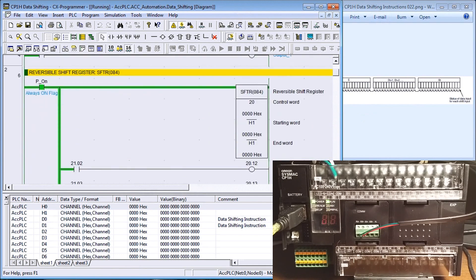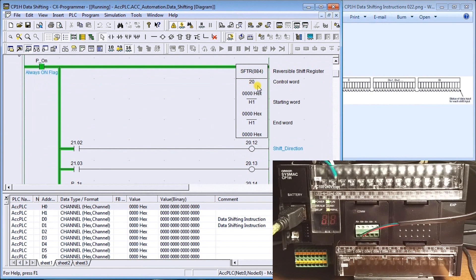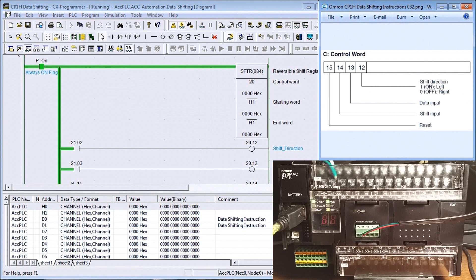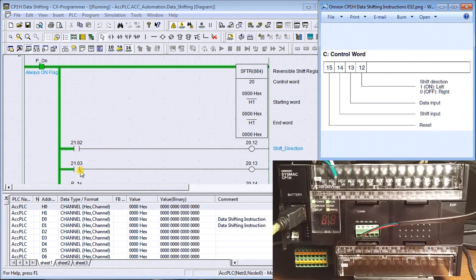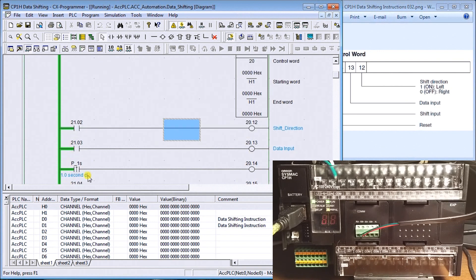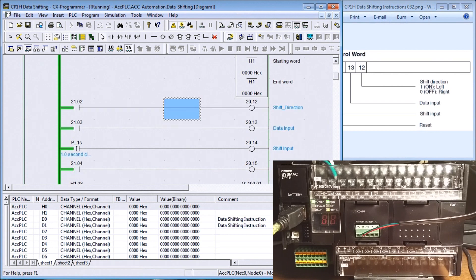Our next instruction is the reversible shift register. It does the same thing except now we can go backwards and forwards. The shift register works on a control word, and the control word tells us: direction, data input, shift input, and reset. Reset basically just clears the register. My control register is input register 20, my starting word is H1 and ending word is H1, so we're dealing with 16 bits. Direction comes from bit 21.02, data input from 21.03, and then the shifting input.